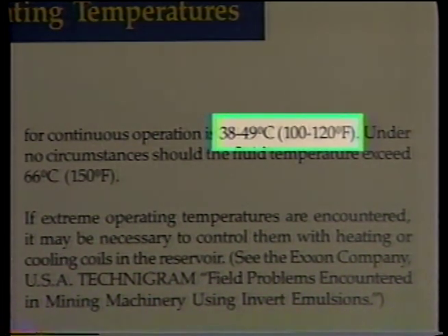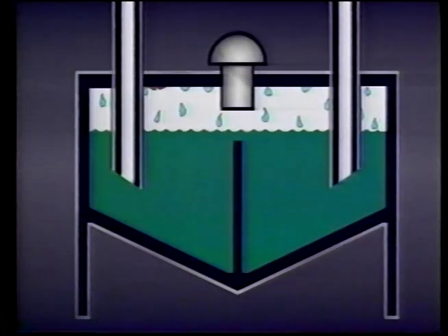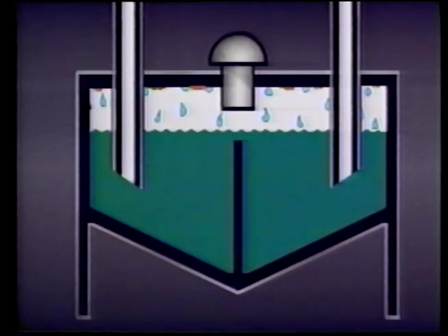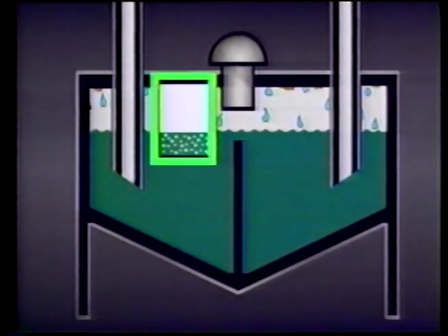Water evaporation from these fluids can cause several problems. Water vapor escaping from the fluid can condense on unprotected metal surfaces, causing rust. Eventually, particles of rust will flake off and contaminate the entire system. Many water-based fluids contain rust inhibitors, but over time, rust will occur anyhow. Evaporation also reduces the fire resistance of the fluid, since less water is available in the fluid.